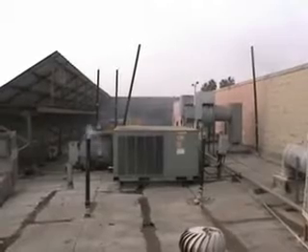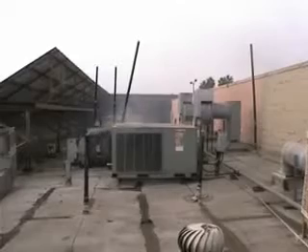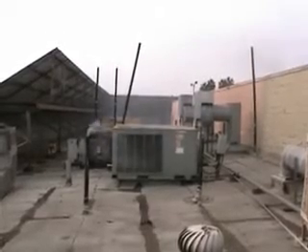So here we are on the roof, same building. And even with the taller than average vent stack — taller than standard vent stack in the foreground here — next to this AC unit, you can clearly see how the smoke just drifts all around this AC unit.